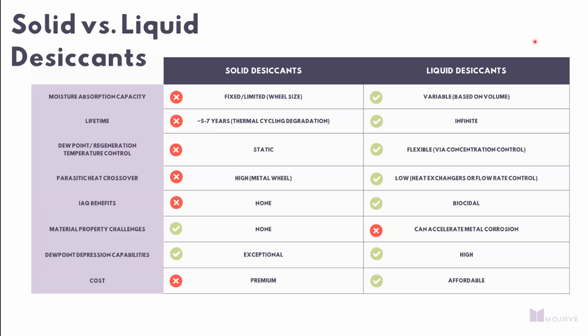On the liquid desiccant side of things, as it's concentration control and your vapor pressure of the liquid desiccant is a function of concentration, you do get a lot more flexibility from a manipulation standpoint. So on a peak day, you could drive up the concentration to dehumidify more. On a part load day, you could relax the concentration to dehumidify less. You're not consuming more energy than you would typically, or than you would want to with a liquid desiccant.